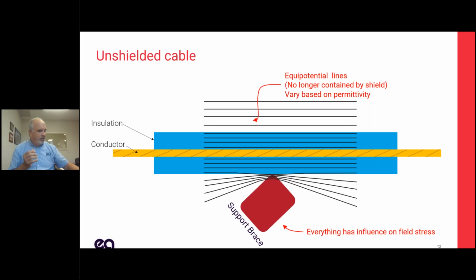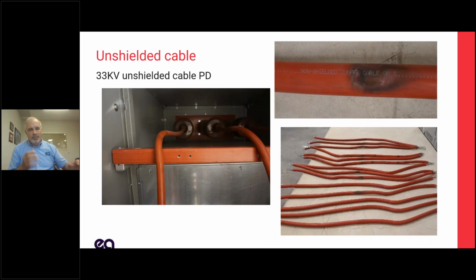Now, very often we'll use unshielded cables inside switchgear. It happens. Here's a picture from one of my customers. They used a jumper cable inside switchgear. Not surprising, I see it all the time. That jumper cable is rated at the operating voltage. But because it's resting on that non-conductive brace, right where that edge is, you get a sharp corner, you get a concentration of field, and you can see from these pictures, they got burn marks. These cables are 4 months old, and they're showing burn marks already. This PD occurred immediately upon energization and was detected via ultrasonic monitoring. It would have led to failure in short order.